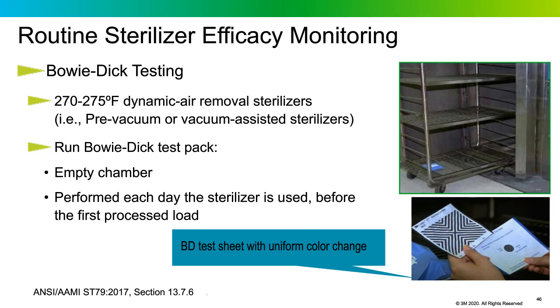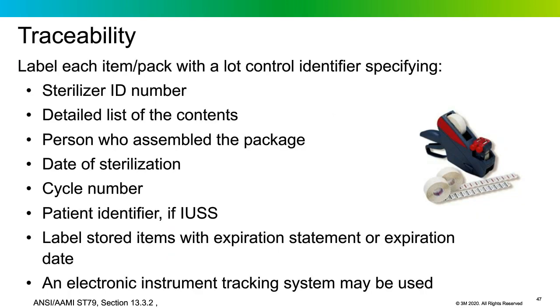AAMI ST-79 recommends that each item be labeled with a load control identifier prior to sterilization. This allows items to be identified or retrieved in the event of a sterilization process recall. Items processed for immediate use should also include a patient identifier, and items stored for later use should have either an expiration statement for event-related shelf life systems or an expiration date for time-related shelf life systems.